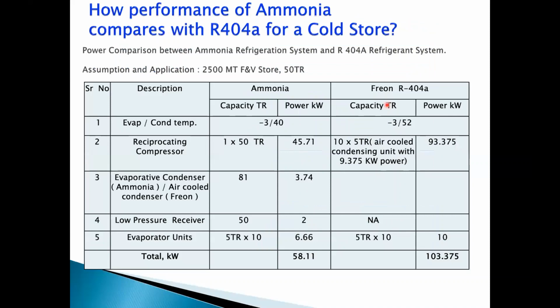These are some of the examples when you compare R404A and ammonia, for a 2,500 metric ton cold store. It has only 50 TR. It's a small refrigeration capacity. But if you look at the kilowatt power required, ammonia requires only 58 kilowatts, whereas Freon, this R404A, needs 103 kilowatts. It's -3 plus 40, -3 plus 52 condensing, because most of these plants are air cooled. And this is all data compiled by the Association of Ammonia Refrigeration through site surveys.